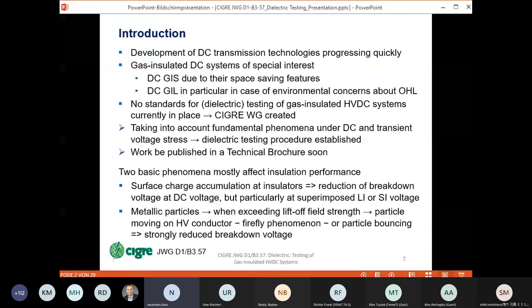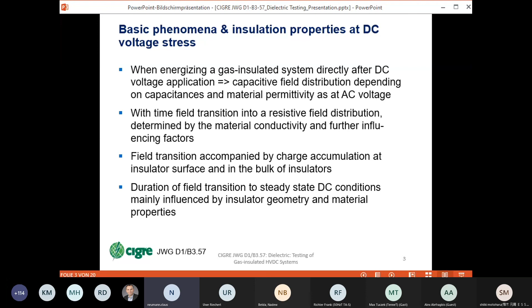Let's consider these basic phenomena and the insulation properties at DC voltage stress. First, when we energize a gas-insulated system directly after DC voltage application, there is a capacitive field distribution, depending on the capacitances and on the material permittivity, as it is at AC voltage. With time, there is a field transition into a resistive field distribution, and that is mainly determined by the material conductivity and also by further influencing factors. This field transition is accompanied by charge accumulation at the insulator surface and in the bulk of the insulators. Further, the duration of the field transition to the steady-state DC condition is mainly influenced by the insulator geometry and the material.